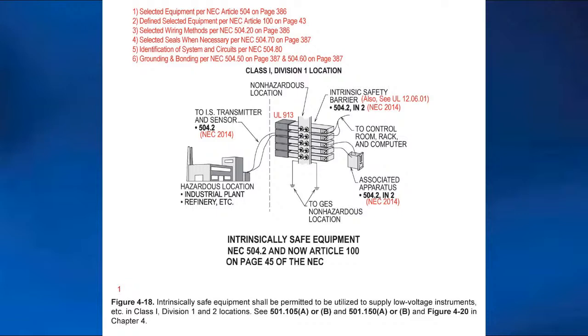And then notice for the barrier, look at what it says: intrinsically safe barrier, UL 12.06.01. Yep. There's a lot of information in there about that, and also UL 913. And then, of course, I just pointed out that 504.2, the informational note 2, was in the 2014 edition, and then all the definitions were moved from 504.2 over into Article 100, and all your definitions for intrinsically safe were put in Part 3. Now they've redone it again for the 2023. I don't know if James covered that with you or not. Not yet. Nope.